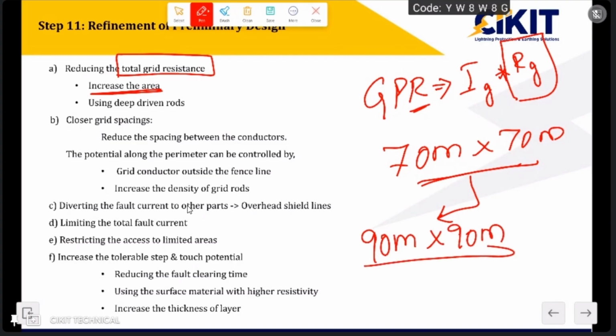So if I'm having a 90 meter cross 90 meter grid, I'm increasing the length and width and we are having more area. Since the area is increasing, the conductors which we are using for the grid also will be increasing, and hence the resistance value will get reduced. If the R value is reducing, then the GPR also will get reduced. So by increasing the area, we can reduce this resistance value. But in most cases, it won't be possible because of the space constraints.